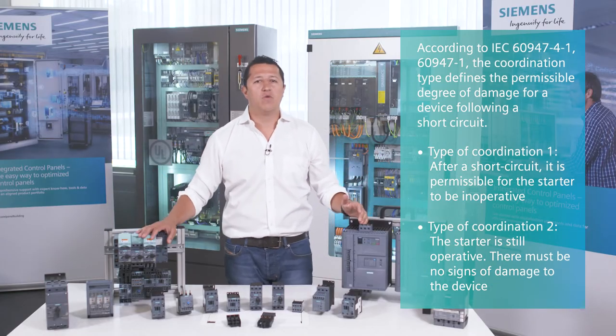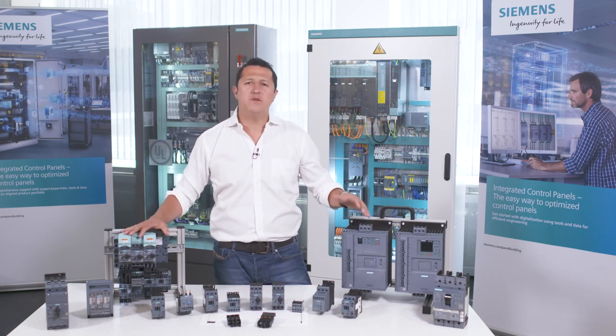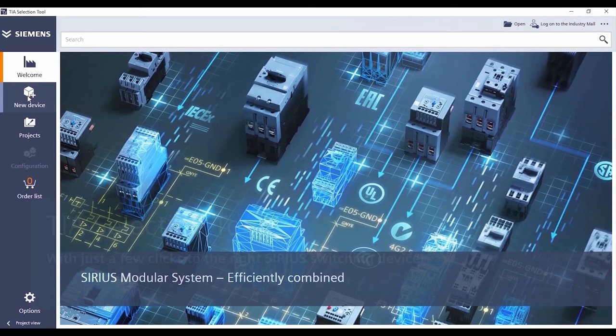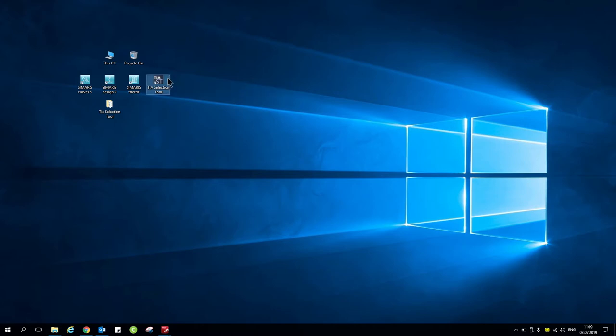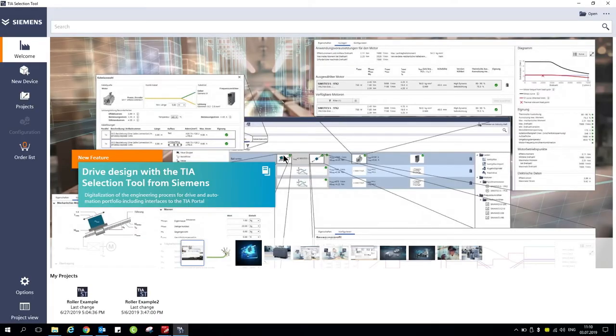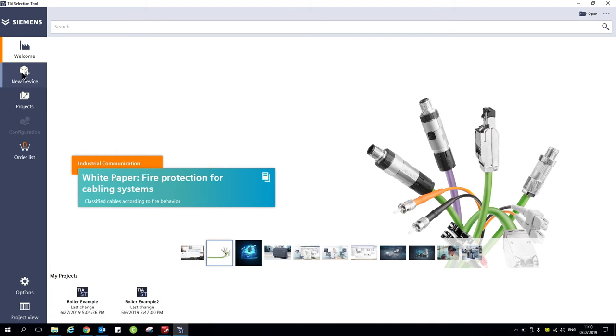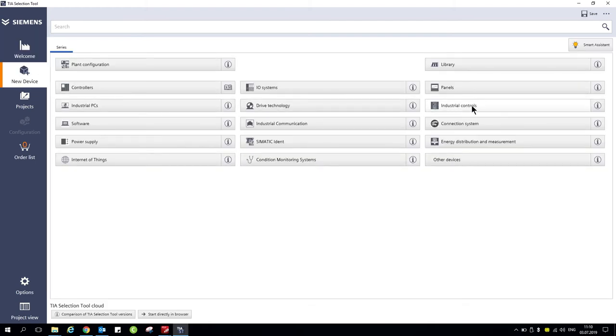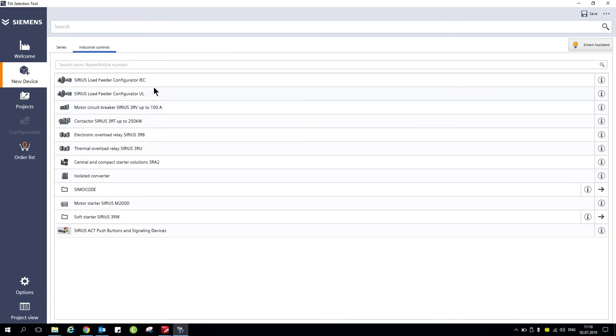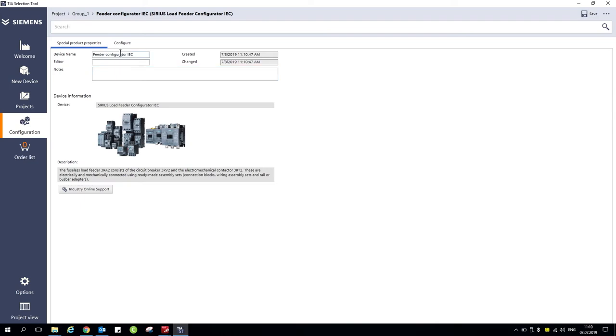A big way of saving time when selecting these load feeders is our TIA Selection Tool. Let me show you how it works. You click and open the TIA Selection Tool. The software is updated approximately every two months — if you see any differences in the user interface or menus, just come back to us. You click New Device, then click in the Industrial Controls menu. In the upper part you will find the load feeder configurations for IEC or UL. The TIA Selection Tool will bring you a type-tested combination in either of these standards. Let's go for IEC.